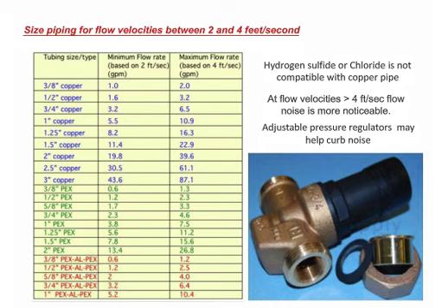And again, I included a little picture here of that happens to be a Honeywell Braukmann adjustable pressure regulator. You can start to drop the water pressure that goes through the heat pump because the heat pump doesn't care what the pressure is, it just wants that flow. So even if the house is running at 60 psi, to quiet the system down, you can adjust that pressure as it goes through the heat pump down as long as you meet that flow. So bear that in mind if you have a noisy system.